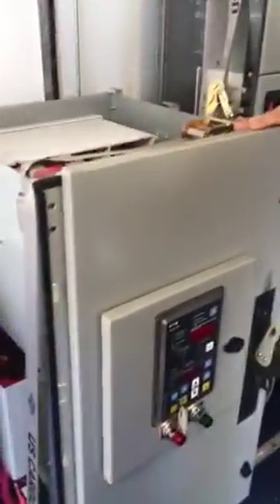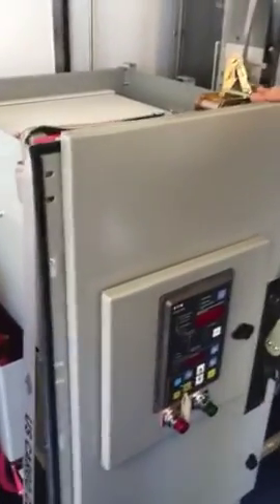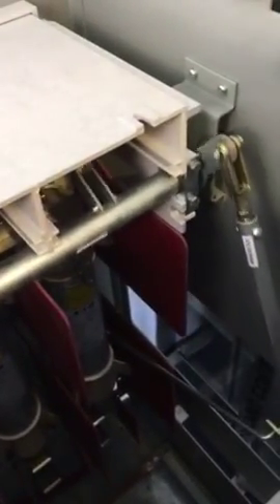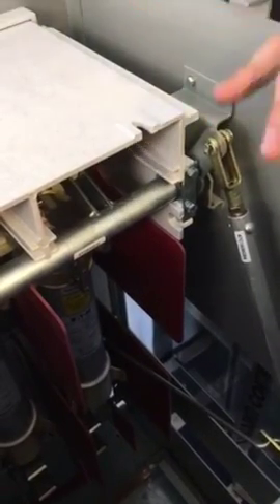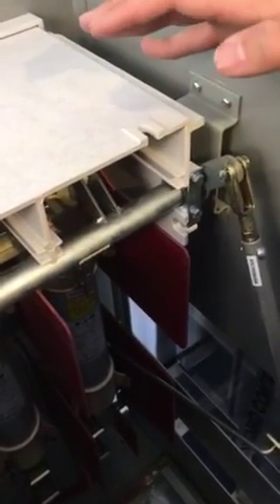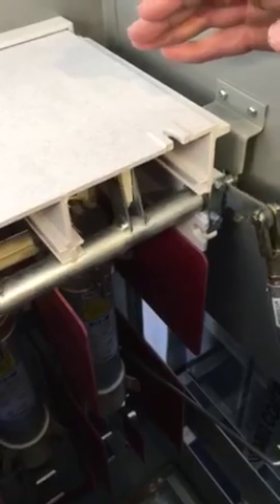Right here we have our only medium voltage equipment in the truck, and it is an Amptector, a retrofilled Ampgard starter. We have taken all of the internals and gone with the newer style isolation switch, which has very few moving parts as compared to the original or some of the older Ampgard styles where the fuses are actually moving. So from a maintenance perspective, these are much more reliable and robust because of the lack of mass with the moving pieces.